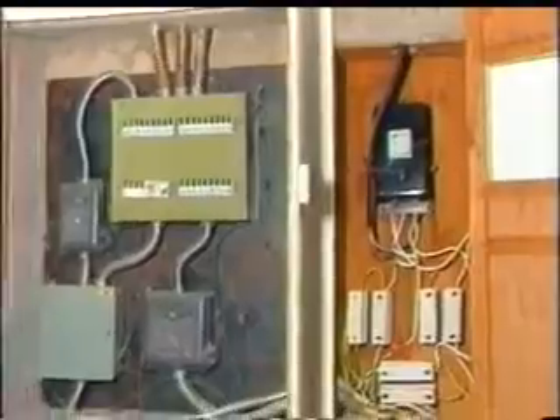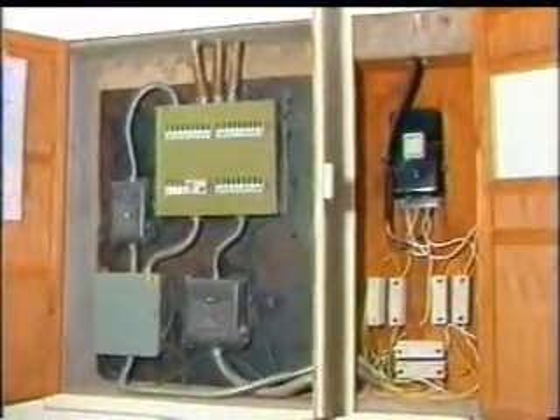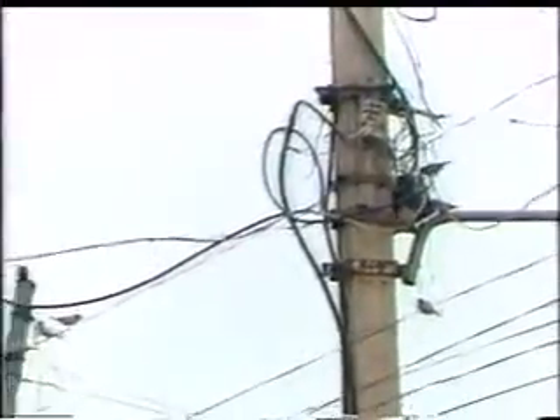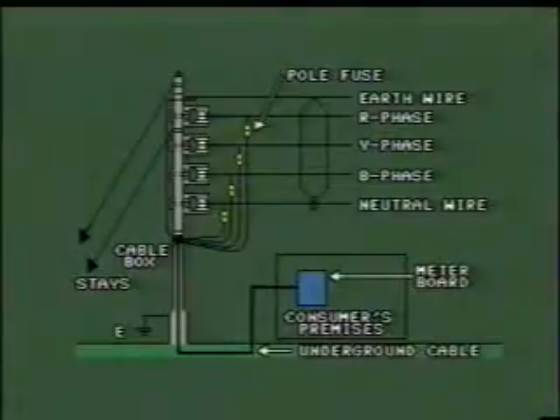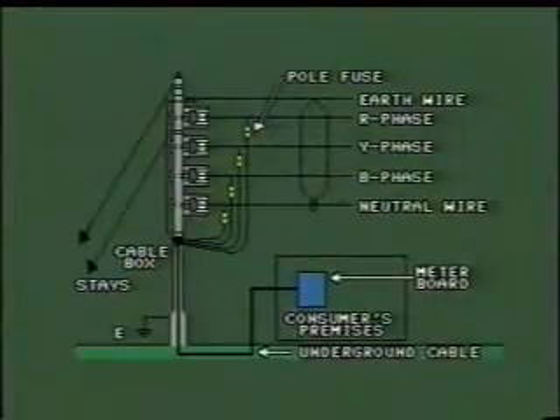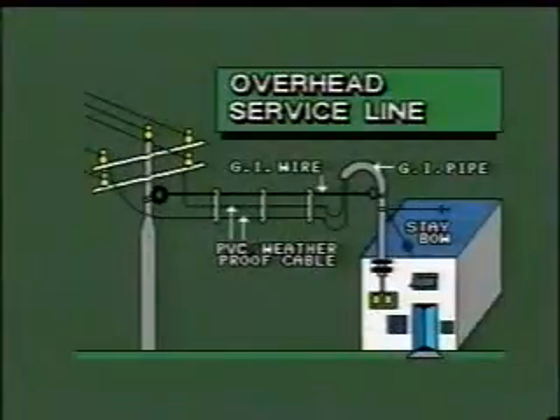A service main is a cable connecting the distribution lines and the consumer main board. Service main should be a cable of standard make and of adequate size to meet the maximum demand of the house. The service main may be overhead or underground. This is how the connections are made for underground service main, and this for overhead service main.